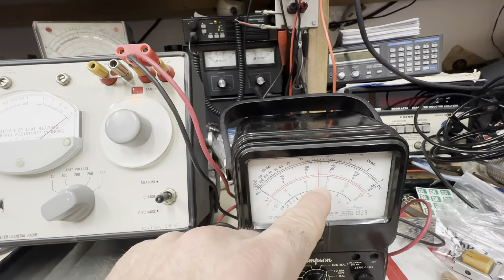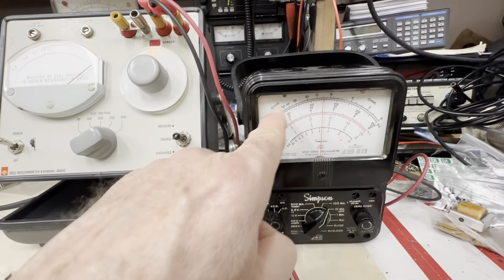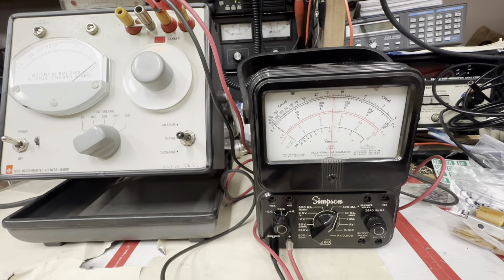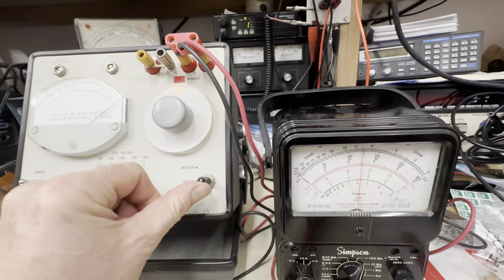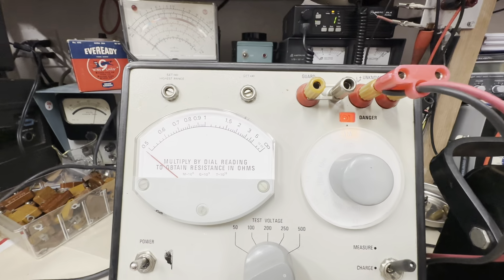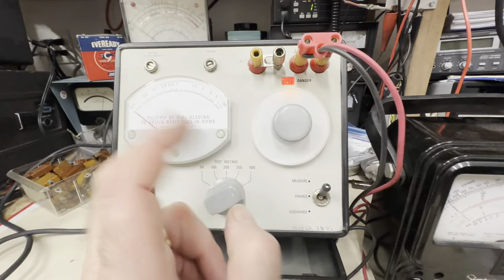And so we've got 500 volts on this. At 500 volts, we have, guess what? 5 mils. And of course, that shows that this is a dead short. Yeah, at least as far as the meter is concerned, the 1863 that is.